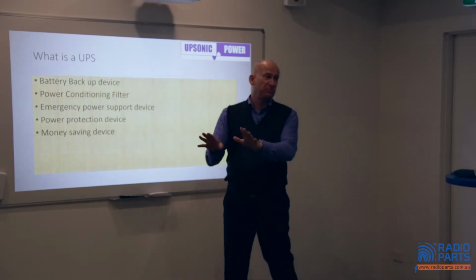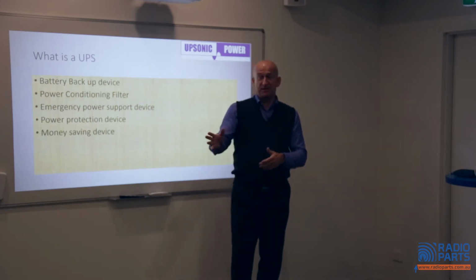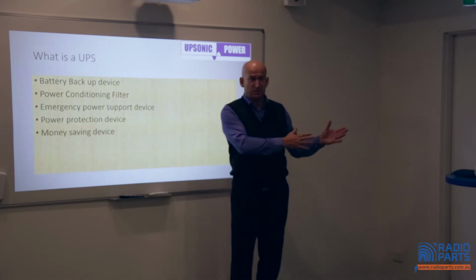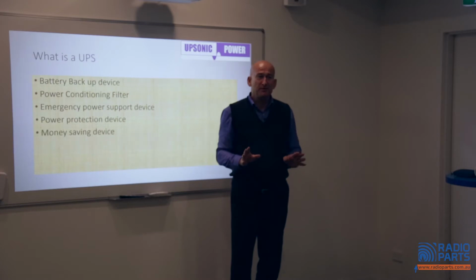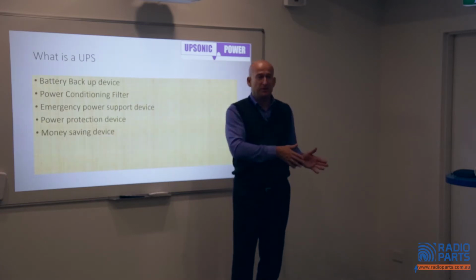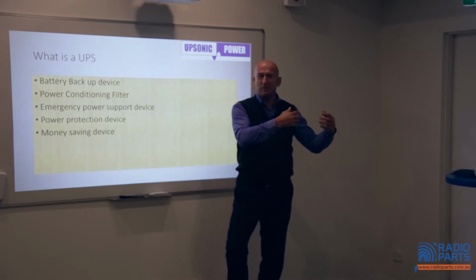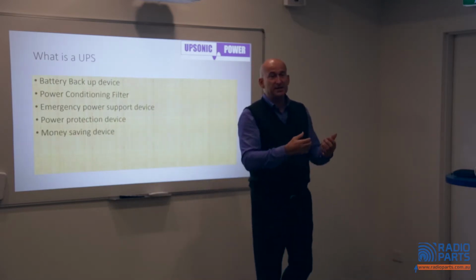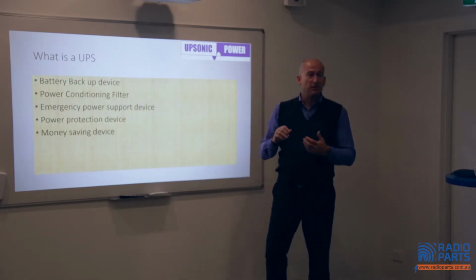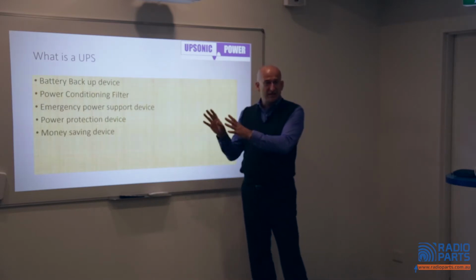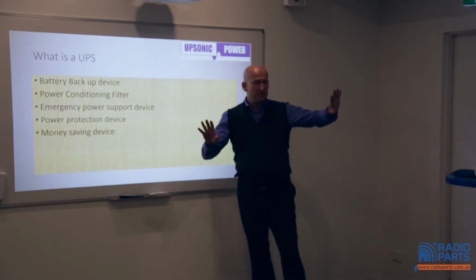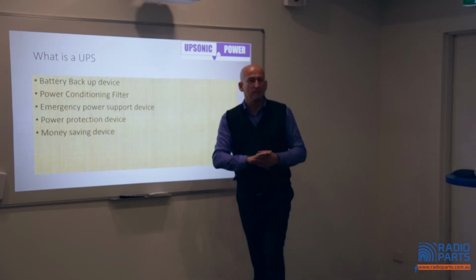And you ask about the equipment it was supporting downstream, and they'll say, that's fine. You'll go, well that's perfect - that's what the UPS should do. You want the weakest link to be the most non-critical item, and in this case that's the UPS. So a UPS is designed to be sacrificial to keep whatever's downstream okay and working.